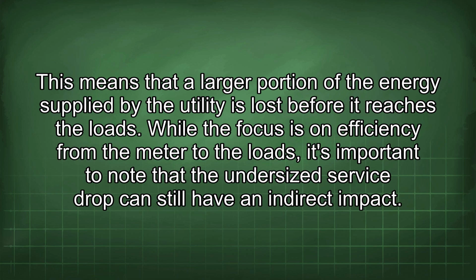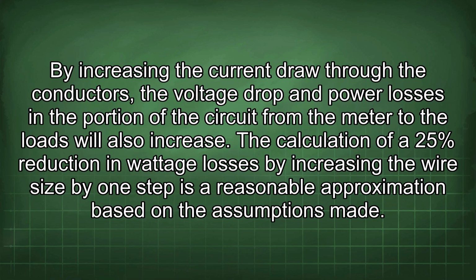While the focus is on efficiency from the meter to the loads, it's important to note that the undersized service drop can still have an indirect impact. By increasing the current draw through the conductors, the voltage drop and power losses in the portion of the circuit from the meter to the loads will also increase.